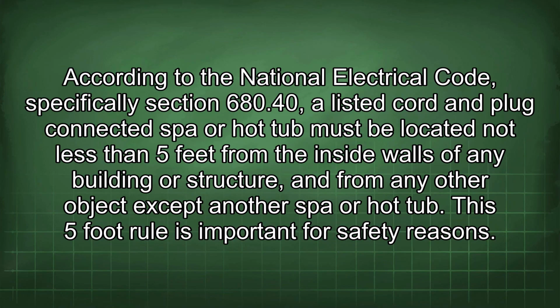According to the National Electrical Code, specifically Section 680.40, a listed cord and plug-connected spa or hot tub must be located not less than 5 feet from the inside walls of any building or structure, and from any other objects except another spa or hot tub. This 5-foot rule is important for safety reasons.